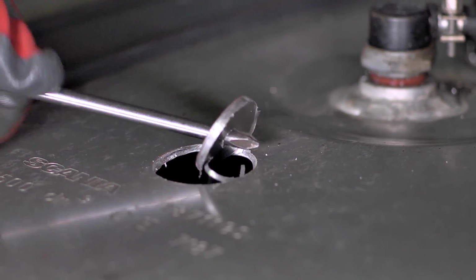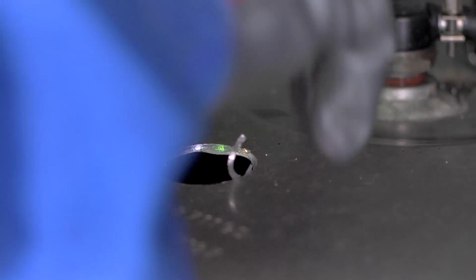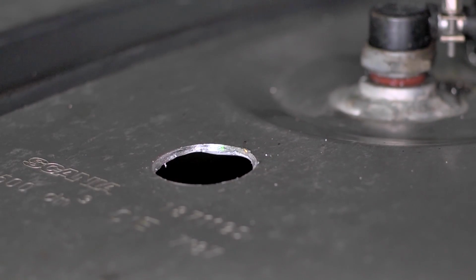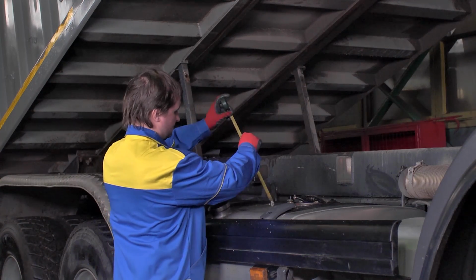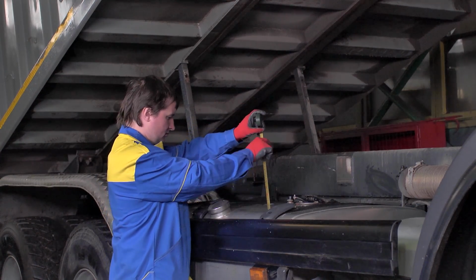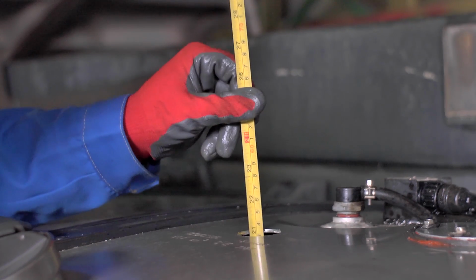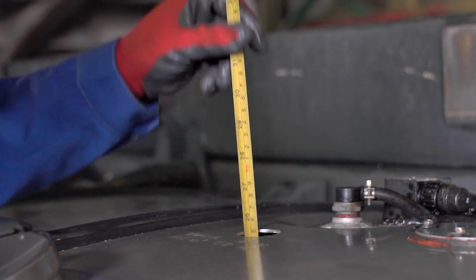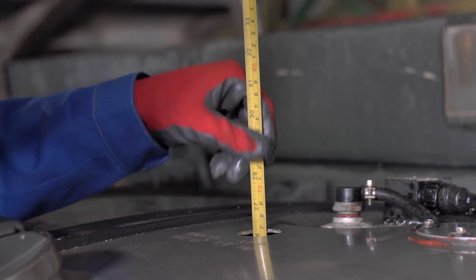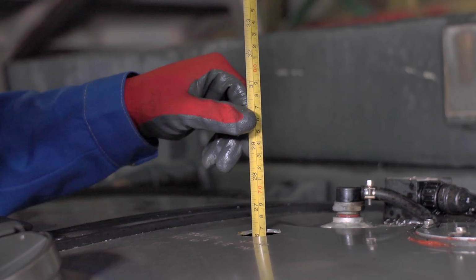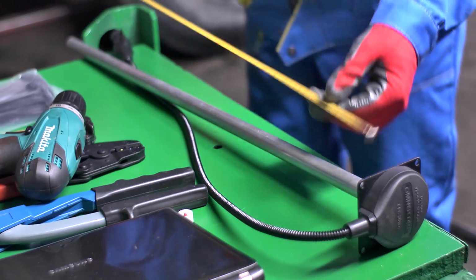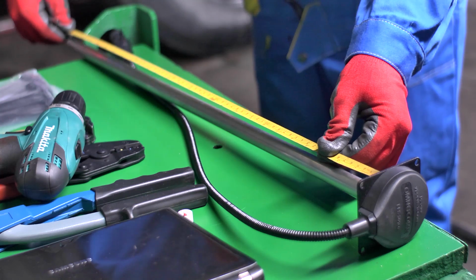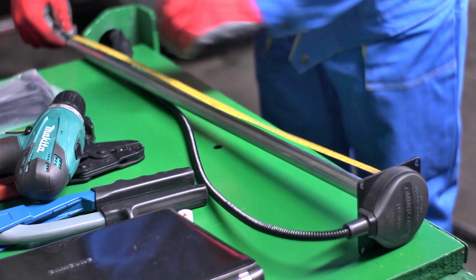The final step of fuel tank preparations involves measuring the depth. You have to measure the depth at the point of sensor installation. When choosing the length of your sensor for a specific fuel tank, remember that fuel residue, water and dirt can accumulate at the bottom of the tank. The sensor must not come in contact with the tank bottom.